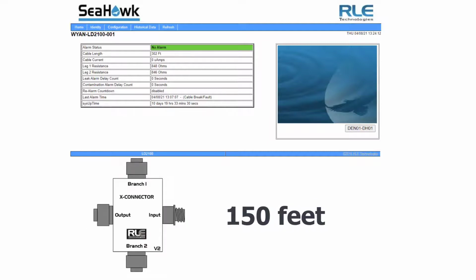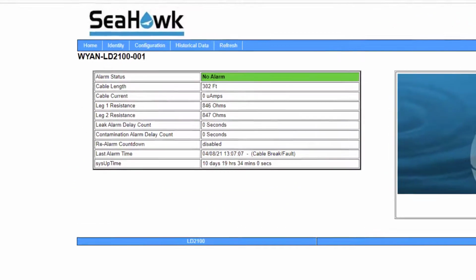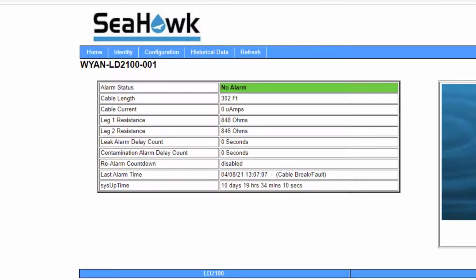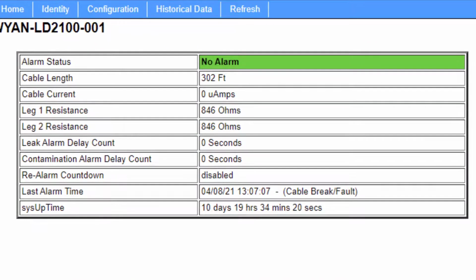And then the third component to keep in mind whenever you're calibrating one of these systems is the optional X connector, which acts as a 3-way branch to split off the leak detection cable, where it simulates 50 feet for each branch. So therefore it simulates a total of 150 feet. Once you have the routing of your cable, as far as any added components that would add resistance to the system, then it's just a simple add up of how much physical cable you have with those simulated devices. That way you have a ballpark of what your overall cable length would be. And then you can look at the leg 1, leg 2 resistance. As I mentioned before, you always want to make sure that there's not a huge variation between those two leg resistance readings. You should be close. Then you'd want to take the average of those two legs and calculate it out to be your ohms per foot, which we can adjust from the configuration menu.